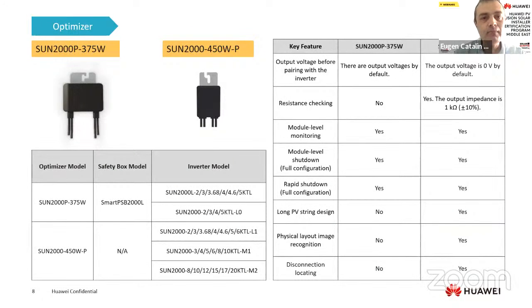Optimizer. We have new type 450 watt optimizer, compared with 375 watts. The old is compatible only with SUN2000-L 2-5 KTL and with a European model L0. The new optimizer is compatible with single-phase residential 2-6 KTL-L1, 3-phase residential 3-10 KTL-M1, commercial inverter 8-20 KTL-M2, and also with the new model M3. So the new optimizer is improved also. Using the new optimizer SUN2000-450W, we will not have voltage on the string compared with the old one. So we need to measure the impedance of the string. Depending on the number of panels and optimizers, we'll have 1 kilo ohm per panel with optimizer, plus minus 10%.